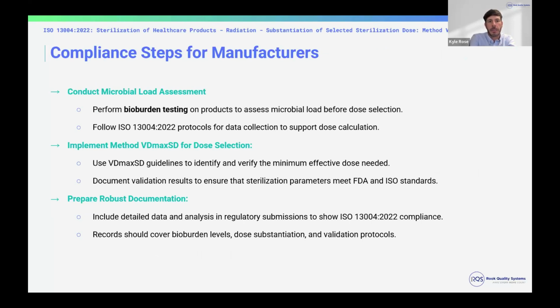Compliance steps for manufacturers: performing the bioburden testing to assess microbial load before dose selection, following the ISO standard for protocols and data collection to support this dose calculation and validation process, using the VD max SD selection guidelines to identify the correct dose, and then documenting the results for your validation and ongoing sterilization efforts going forward. And then again, make sure you align with the current version of 13004. Records should be maintained in your quality system. If you're doing a regulatory submission, your validation process is likely going to be submitted with your regulatory submission, and then the ongoing records of sterilization and the dose meeting your requirements will need to be reviewed, approved, and maintained in your quality system for future audits and compliance.